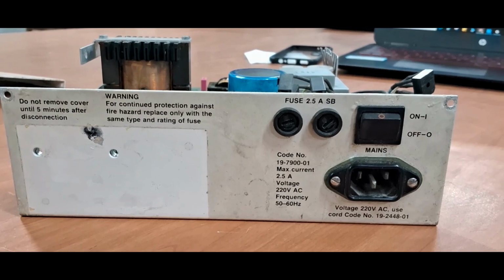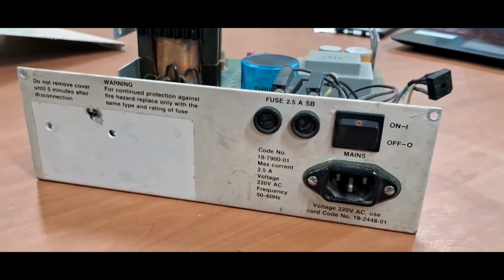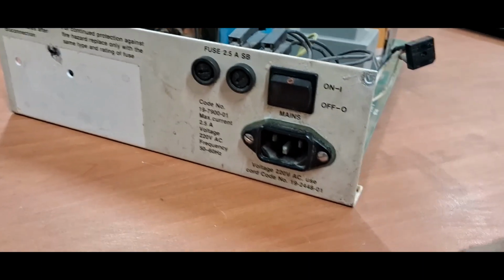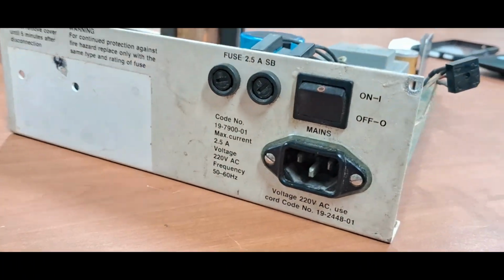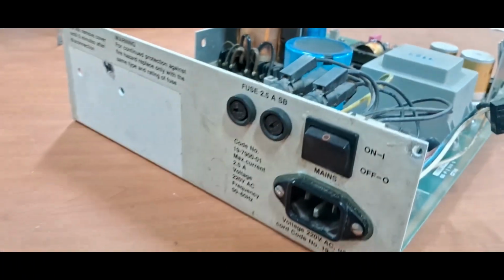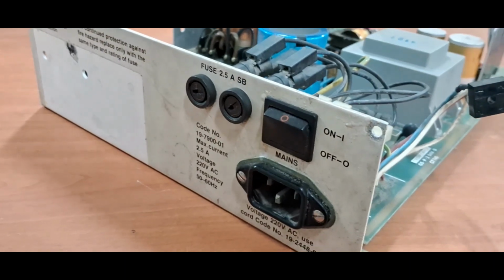This is the back of the unit. This is where the mains power comes in. That's standard 220 volts AC. It uses an IEC connector, a C13 C14 pair, and there's two fuse holders over here and one main switch.